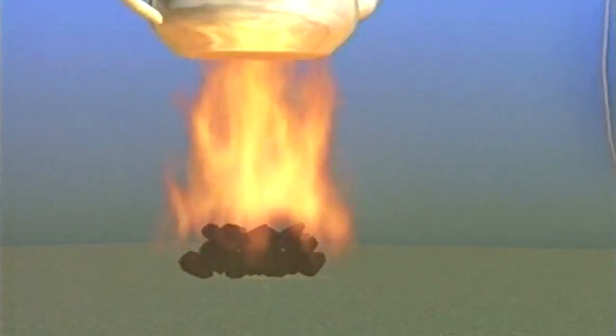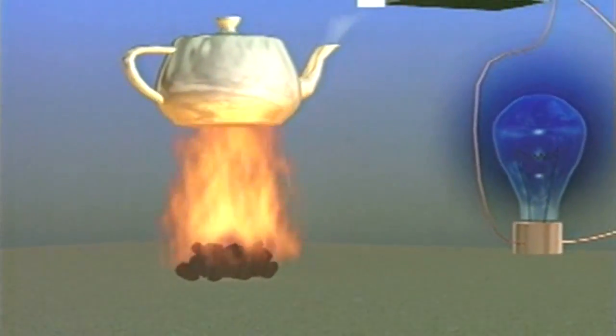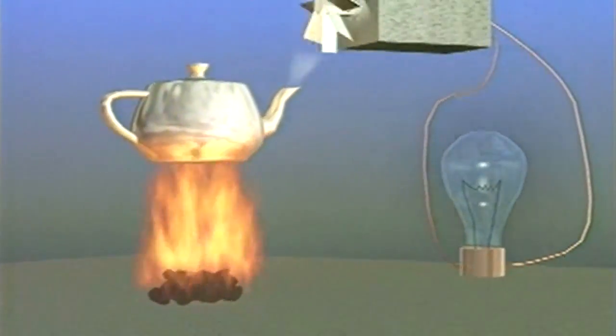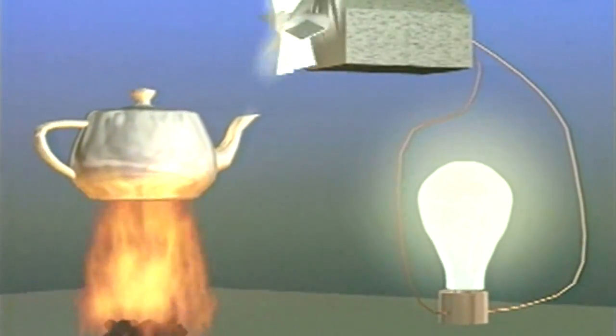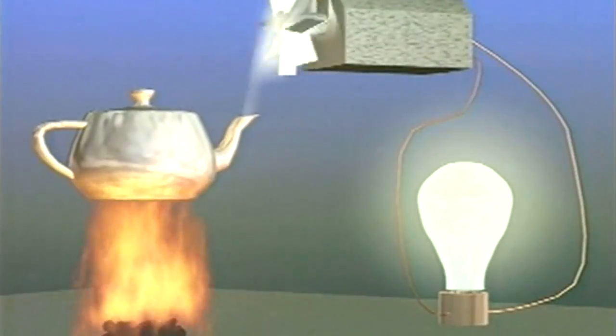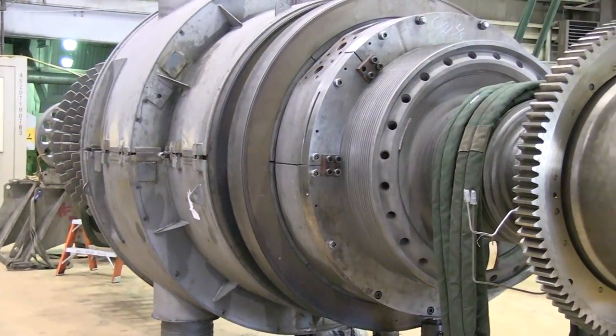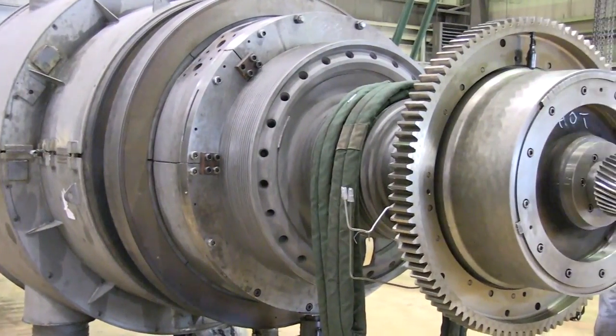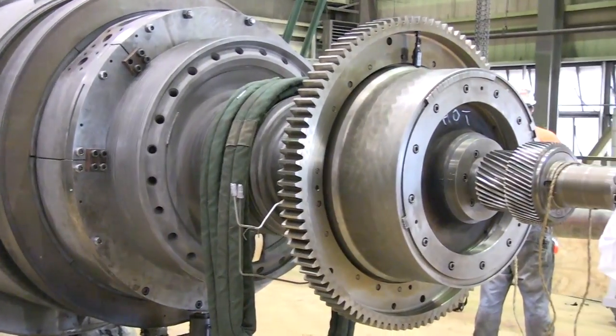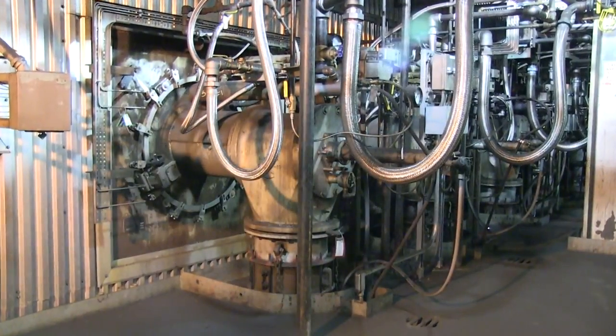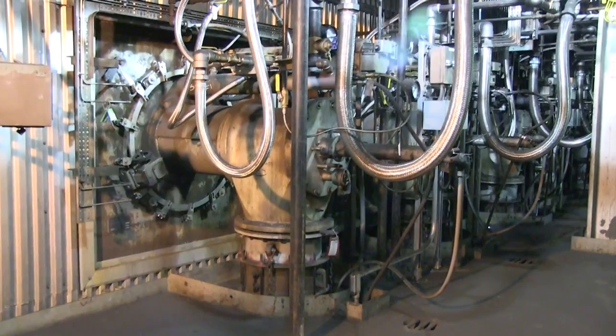The coal is burned to heat water in the boilers into steam. The pressure of that steam turns a turbine, which turns a generator, which produces electricity. Even though the physics of how it works is simple, the technology is not.